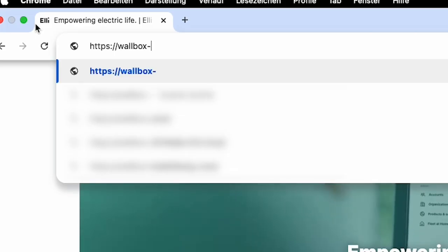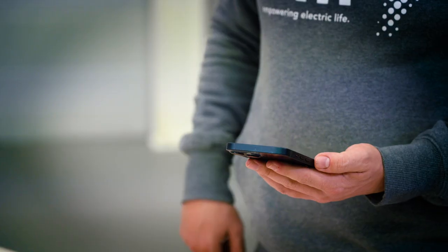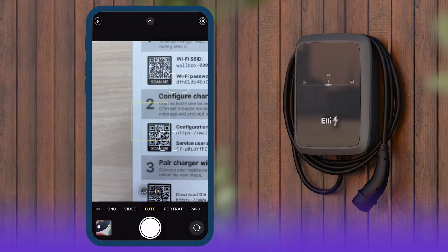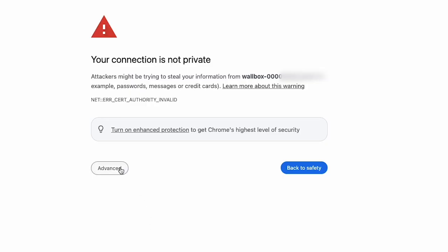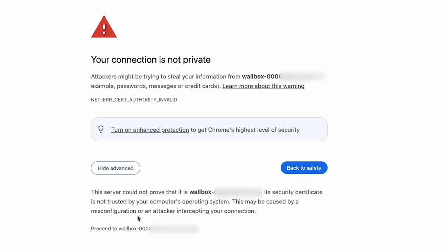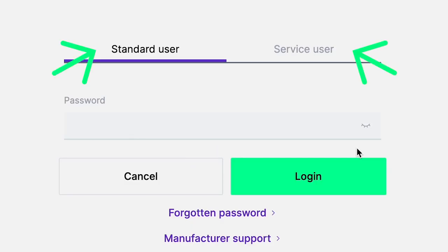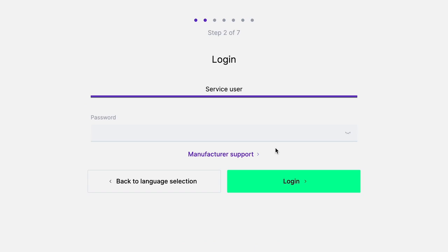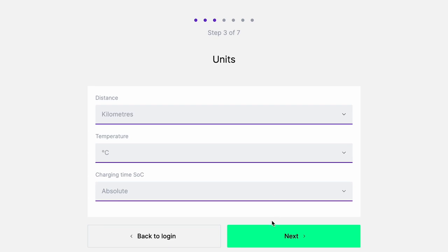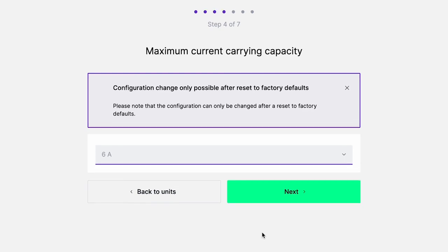Enter the host name in the address bar of your web browser or scan the second QR code on the access card. We recommend using the Google Chrome browser. There are two different user roles to control the Elli Charger 2. In the Service User profile, extensive rights are available for configuration. Log into the wall box configuration using the Service User login data provided. Follow the instructions displayed in the browser.